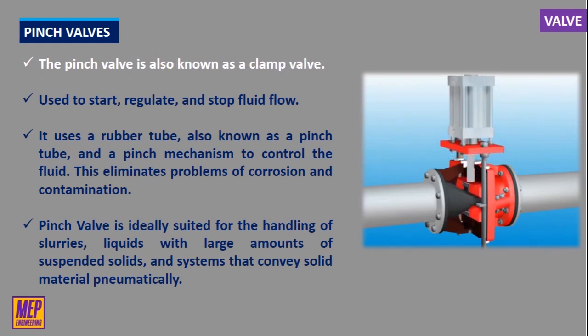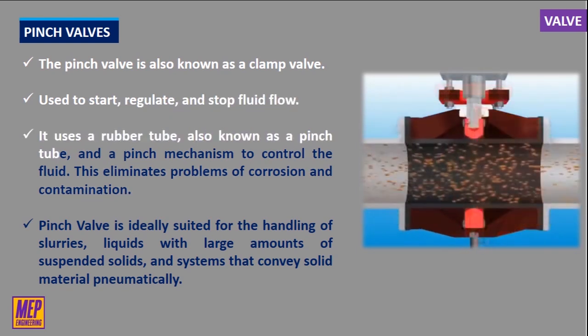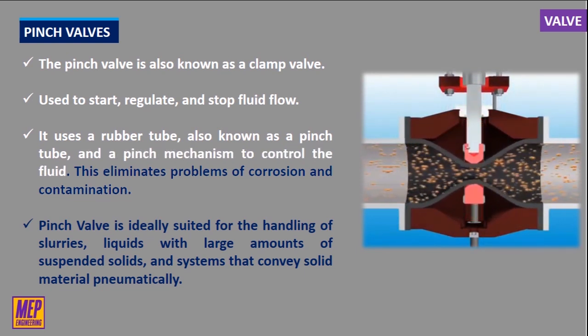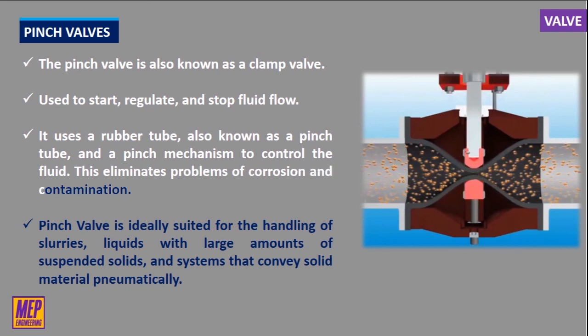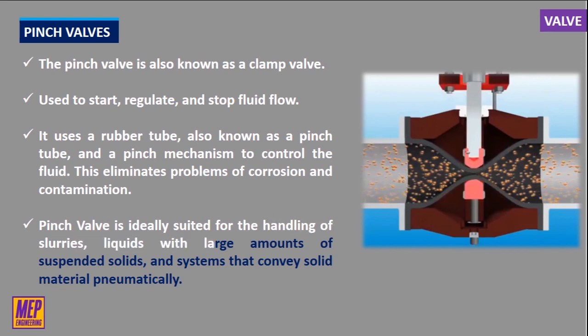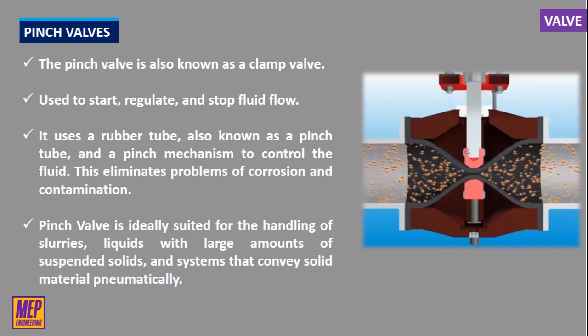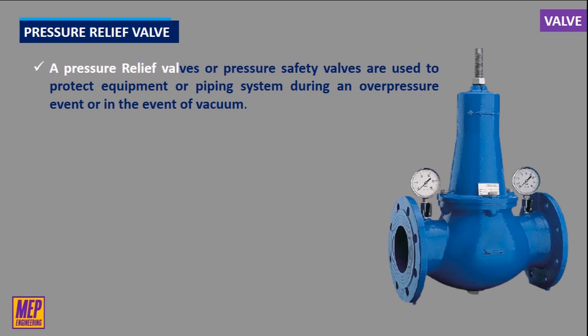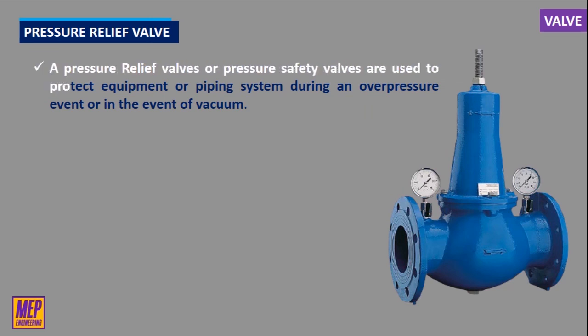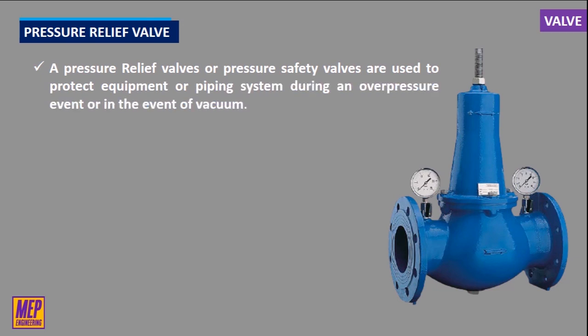The pinch valve, also known as a clamp valve, is a linear motion valve used to start, regulate, and stop fluid flow. It uses a rubber tube, also known as a pinch tube, and a pinch mechanism to control the fluid, which eliminates problems of corrosion and contamination. Pinch valves are ideally suited for handling slurries, liquids with large amounts of suspended solids, and systems that convey solid material pneumatically. Pressure relief valves, or pressure safety valves, are used to protect equipment or piping systems during an overpressure event or in the event of vacuum. This valve releases the pressure or vacuum at a predefined set pressure.